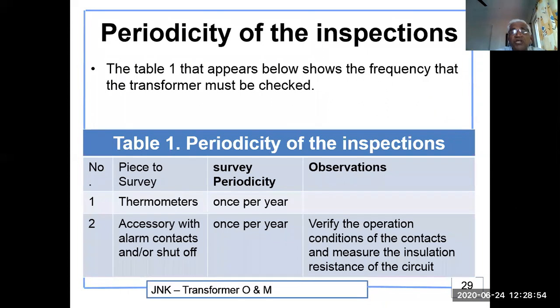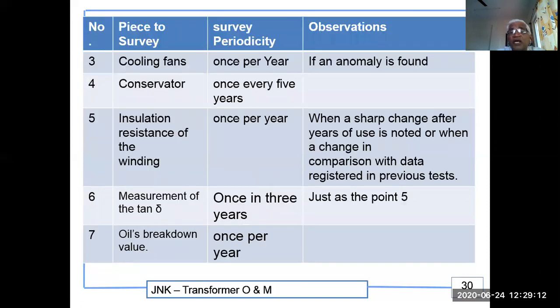Periodicity of inspection. The table shows that number one, thermometers and accessories with alarm contacts, once in every year, and verify the operation conditions of the contacts and measure the insulation resistance of the circuit. Cooling fans, once per year if any anomaly is found. Conservator, once in every 5 years you can clean it. Insulation resistance of the winding, once per year, and when a sharp change after years of use is noticed, then a change in comparison with the data registered with the previous tests.